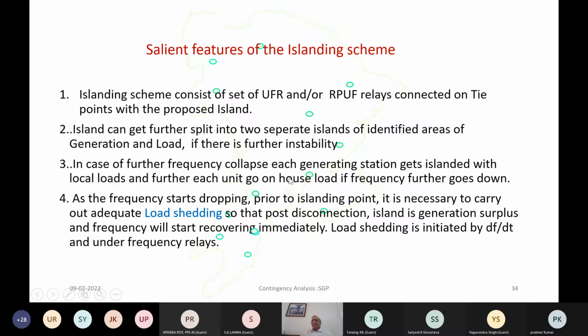In case of further frequency collapse, each generating station gets isolated with local loads, and further each unit goes on house load if frequency goes down further. That means in spite of splitting an island or creating sub-islands within the island, if the frequency continues to sink because load is higher than the generation, then at least the generating stations should be isolated from the load by bringing them to house load. The idea here is that if you are operating on house load, the generation is available for reconnection very quickly, so the restoration of the island can be done faster. That is the idea, and this is then called unit station islanding.